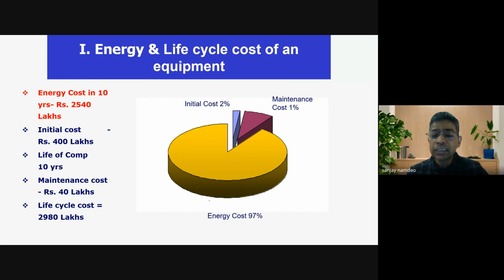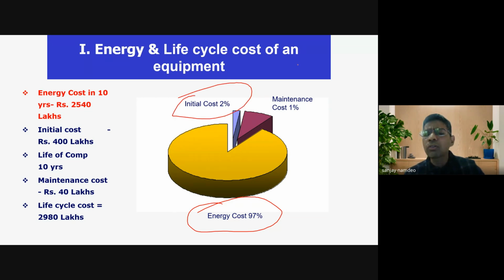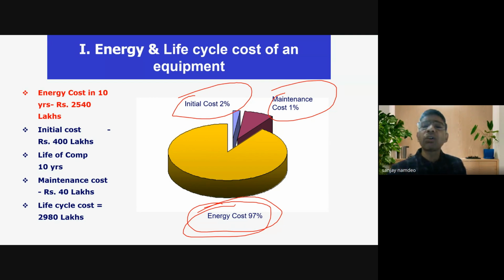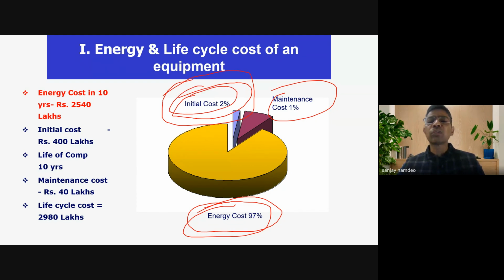So here you can see the energy cost consists of more than 95% of the total cost in the lifetime of that equipment. And initial cost is hardly 2 to 5%. In this case, it is hardly 2%. Maintenance cost is also in the range of, let us say, 1 to 5%. But broadly, the energy cost would be around 90 to 95%. Right. So it means the energy component in the life cycle cost is significant. But on the contrary, what is happening in industry is that whenever a new equipment is purchased, the decision is mostly taken based on the initial cost. And still that L1 approach is prevalent in India, that most of the purchase decisions are based on the initial cost rather than the life cycle cost.